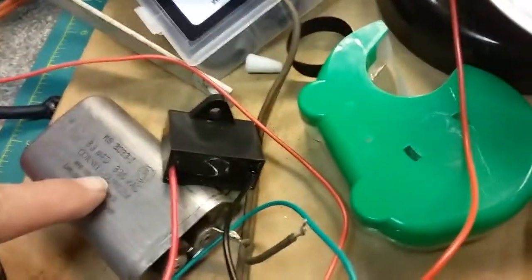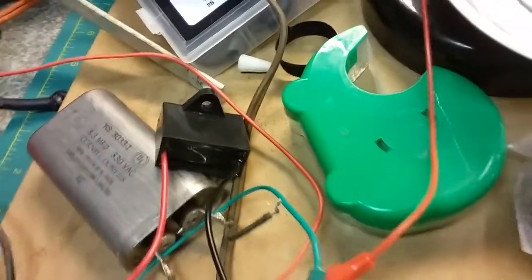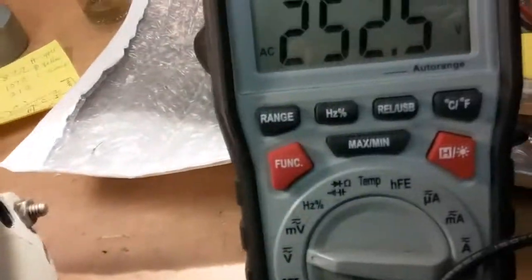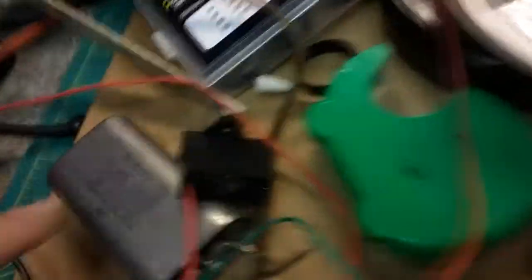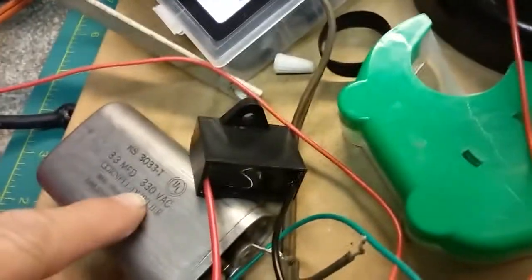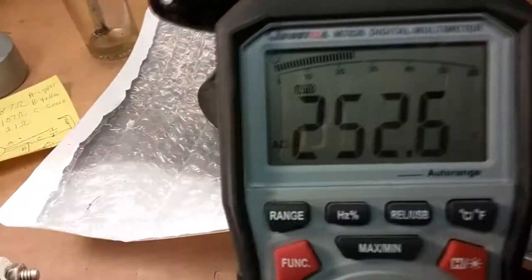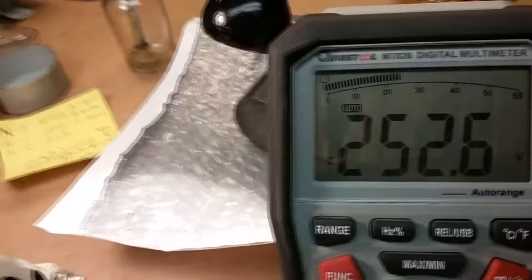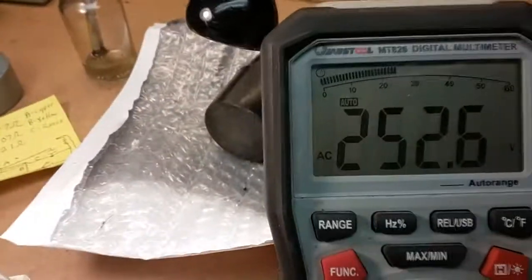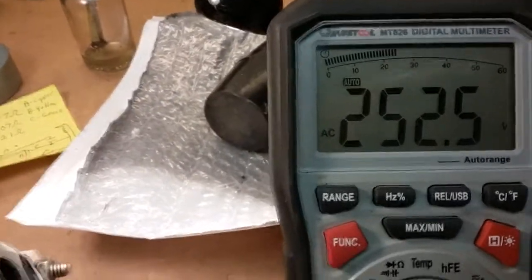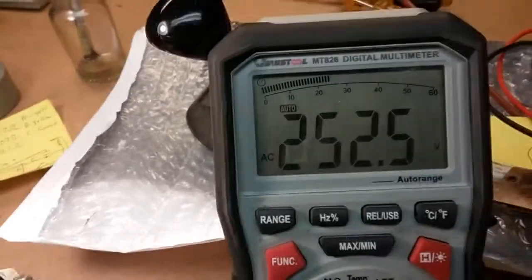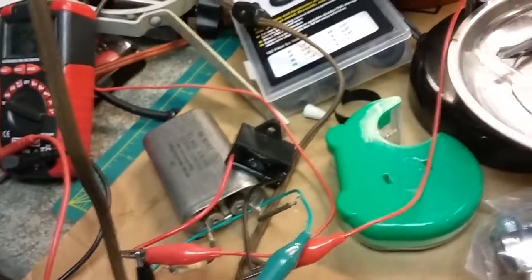The original one was rated at 330, but with the higher mains we were pushing this one to its max. It would be well over 250, so it would be really close to the 330 max that that metal capacitor can stand because of the high voltage today.